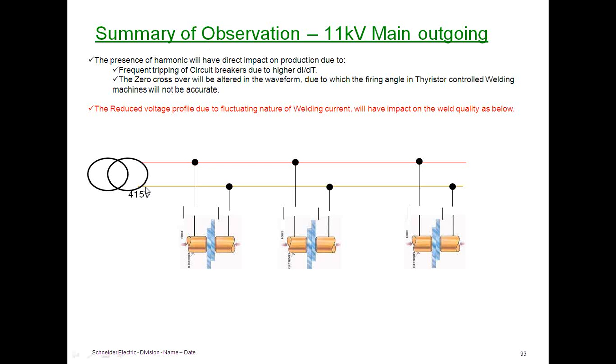This is a welding shop arrangement schematic we have. Let's say we have a transformer here and outgoing feeders going to all the single phase spot welding machines. Let's assume the spot welders are in the off condition, we'll get full voltage on the bus. Say 400 volts on the bus. If the first machine is on, there's a current flow and there's a drop because of the flow of current. Let's say the drop is 5 volts.